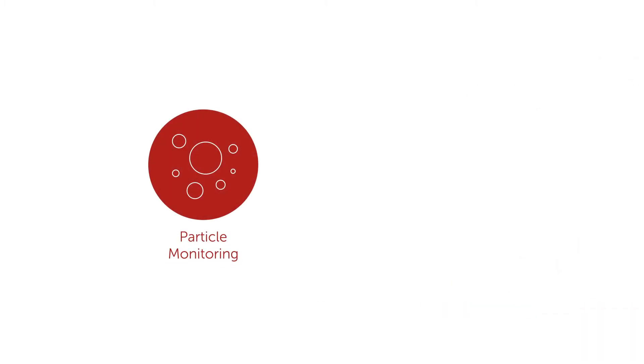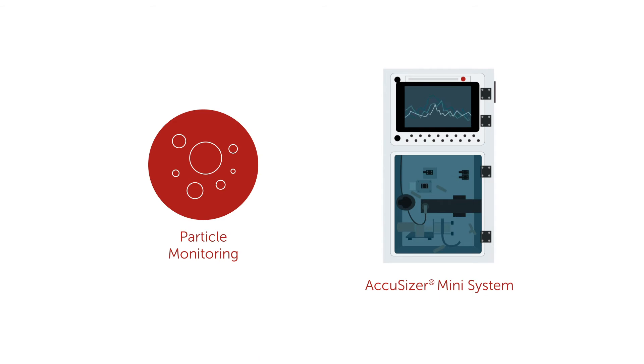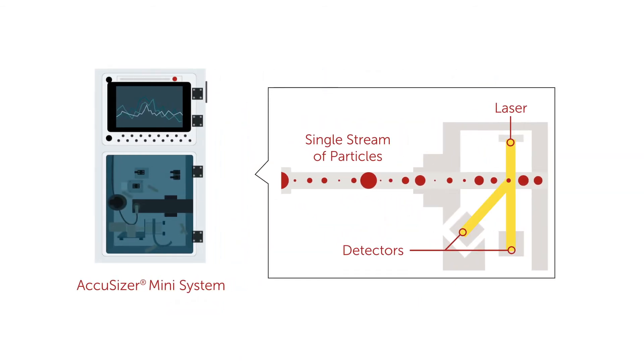Next, large particle count in the slurry is monitored using the AccuSizer Mini system. Slurry particles must be constrained to a defined distribution to prevent damaging wafers during CMP. Using the AccuSizer Mini system to continuously analyze samples, large particles can be detected before they cause harm.